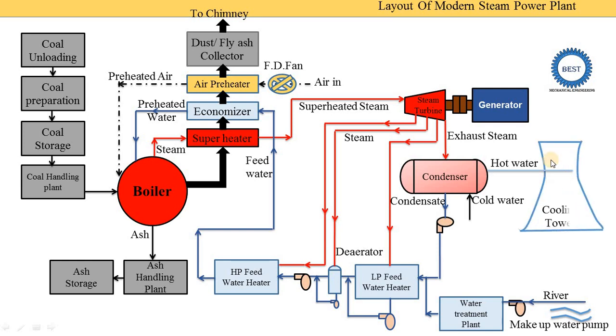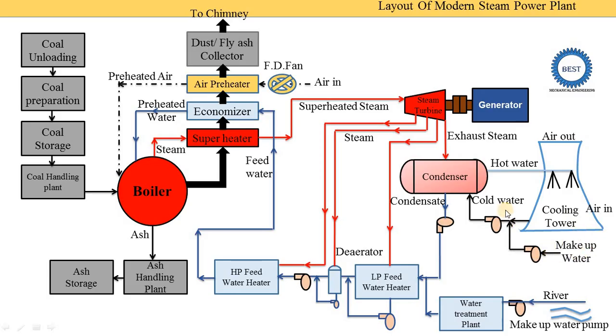In the cooling tower, hot water is sprayed from the throat portion, and air enters from the lower portion. Using atmospheric air, the hot water temperature is reduced. The cooled water is collected at the bottom of the cooling tower and pumped back to the condenser — this is the closed circuit. There is also evaporation loss in the cooling tower, so makeup water from the water treatment plant is added to compensate for this loss.